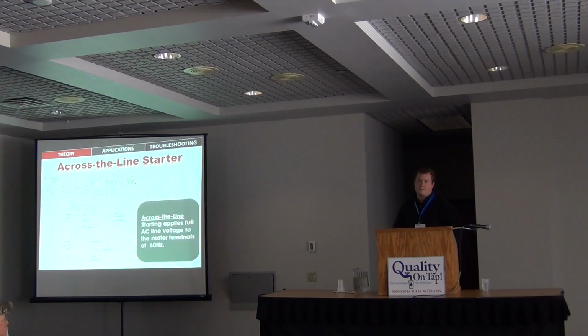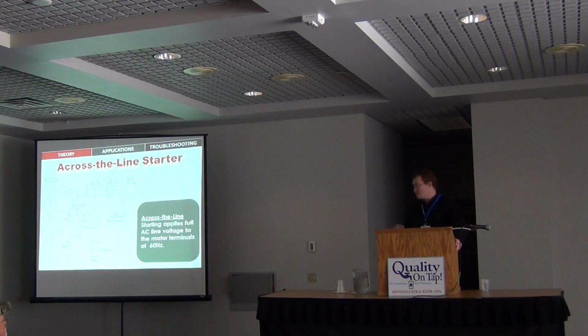Hopefully everyone here that works on pump stations, lift stations, wells, distribution, water plants, or wastewater plants has motors, because if you don't, you're not moving water in most cases. The way it's been done in the past, and the way we continue to do it depending on the situation, is an across-the-line starter. A starter has a contactor or relay that low voltage is applied to, and it pulls in these contactors, which are rated at the amperage of the motor, closing them and applying full line voltage across the motor at 60 hertz.